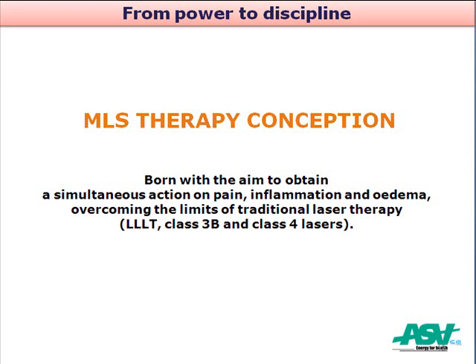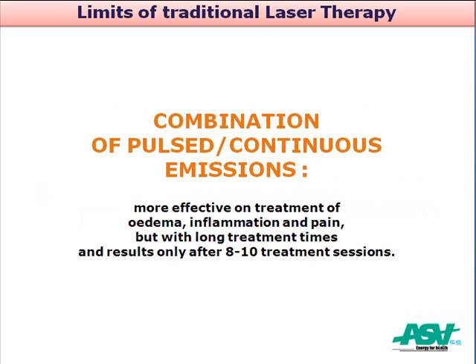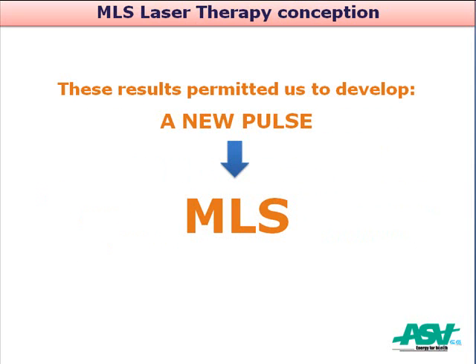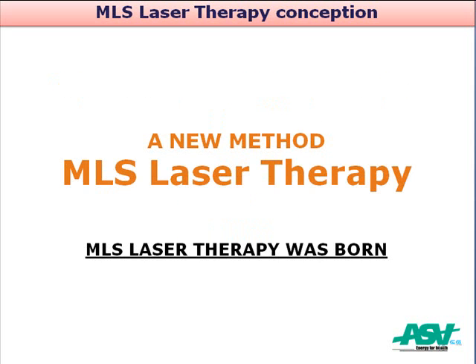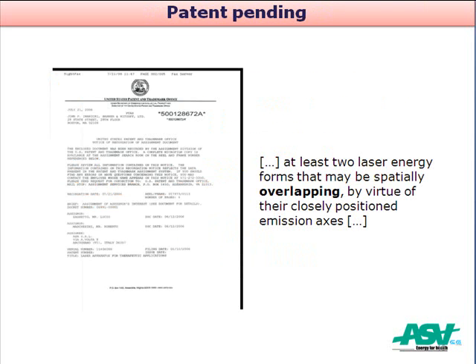The limit with class 4 is actually the thermal effect — there was a strong burning thermal effect and you can actually burn the patient if not applied properly. So one of the challenges was how to combine two pulses to get the maximum effect and how to be more effective in treating edema, inflammation, and pain without the long treatment time. These results led to the development of a new pulse called the multi-wave lock system, and MLS laser therapy was born.